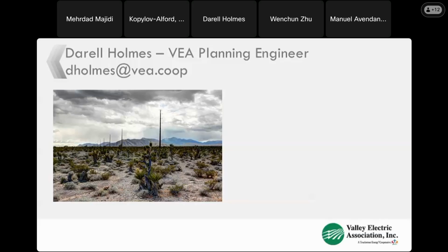But that's to be negotiated too in the future, because VEA's distribution voltage is 29 kV, 26.5 kV. So there will be a conversion from 230 to a lower distribution voltage - yes, to be worked out. But for our modeling and for the system impact study stage, we're focusing on the impacts on the transmission grid, so that's okay, 230. In general, though, there will end up being 2 different substations.